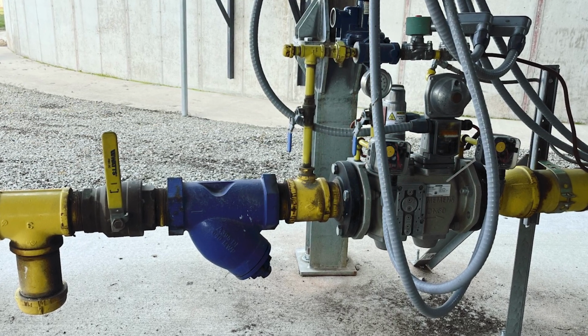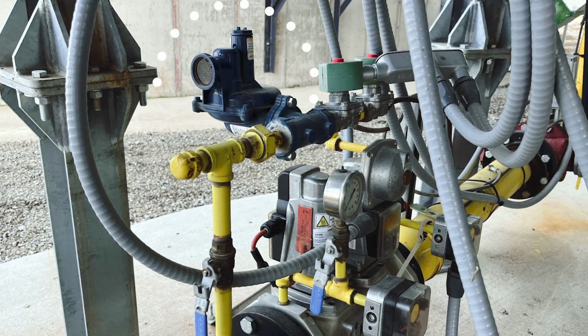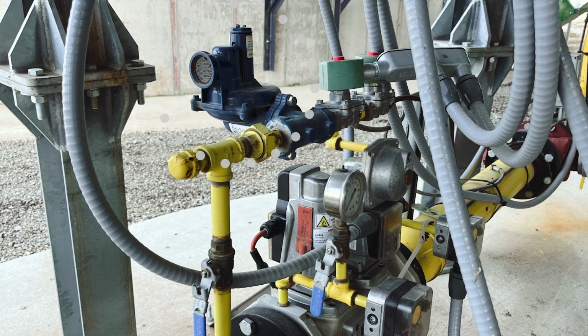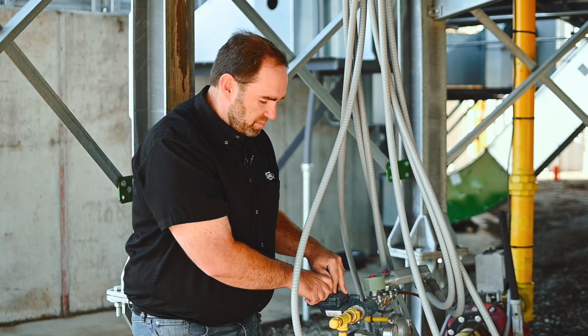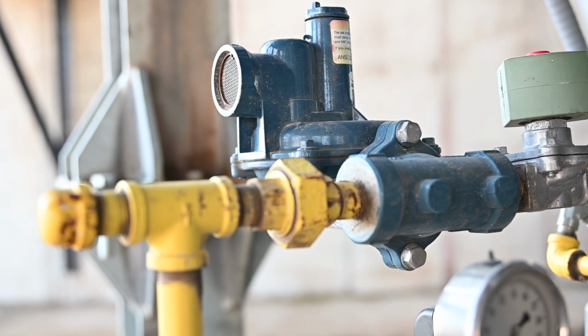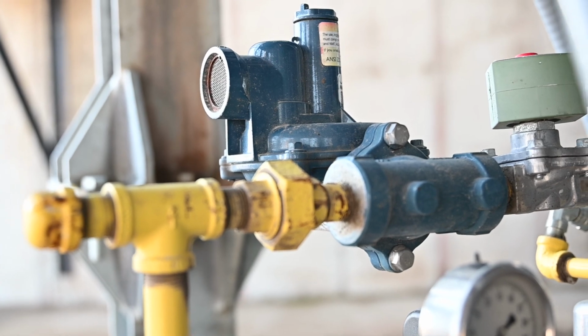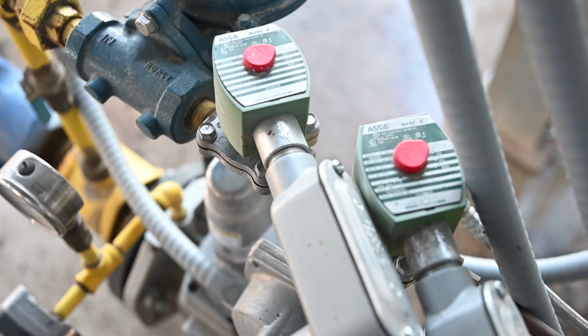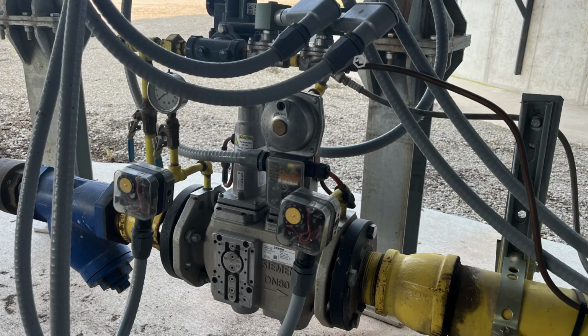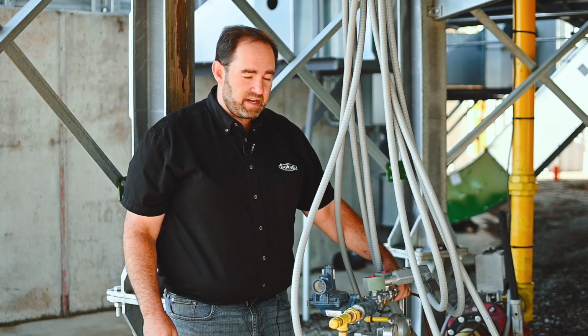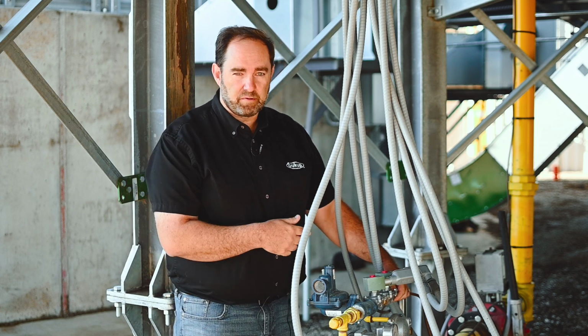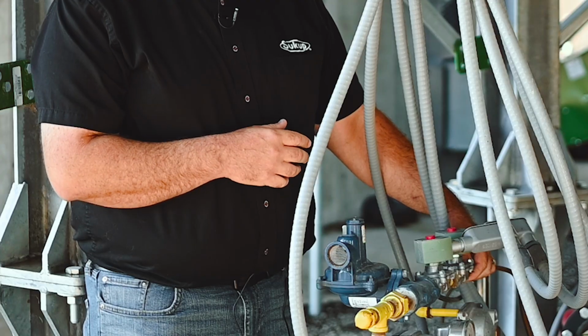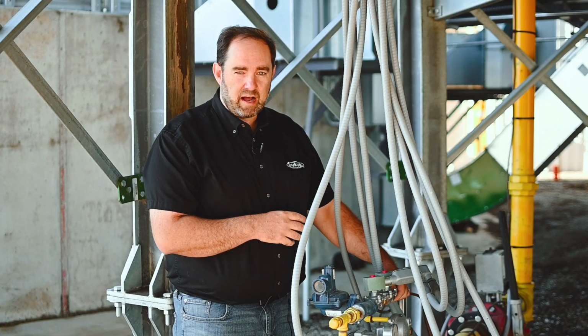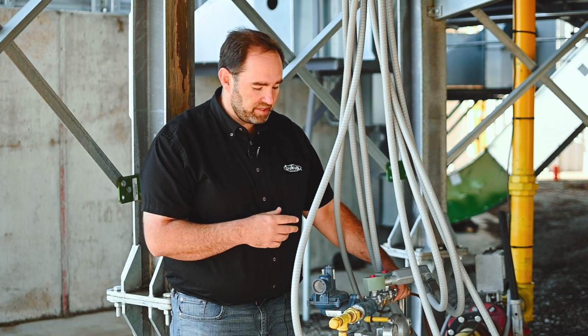The next thing that we come to in the pipe train is a T and a small line that comes up to a regulator and two solenoid valves. This is the pilot circuit. The pilot regulator is basically factory set. You shouldn't have to adjust that. And then it has two ASCO solenoid valves, just on-off valves. Then there's a copper line that goes all the way up into the burner. If you have trouble getting a pilot line to light, sometimes you have to take this loose and blow pressurized air up through there. It is possible that water could get in the copper lines and have to be blown out.